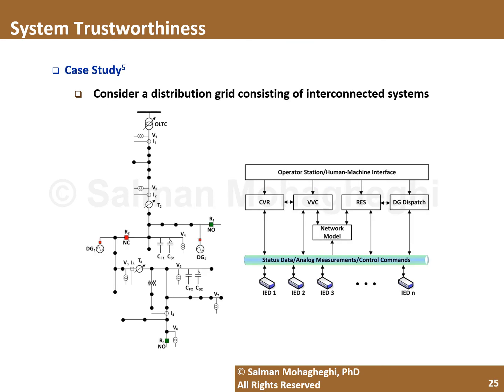We used this concept in an interesting case study, and we demonstrated it for a small scale distribution feeder. So imagine you have this feeder here, you have your distribution substation, this is your transformer with tap changer, and then you have various voltage transformers and current transformers that are connected in different places. You have fixed and switched shunt capacitors, you have a couple of DGs, and then you have some voltage transformers, one here and one here.